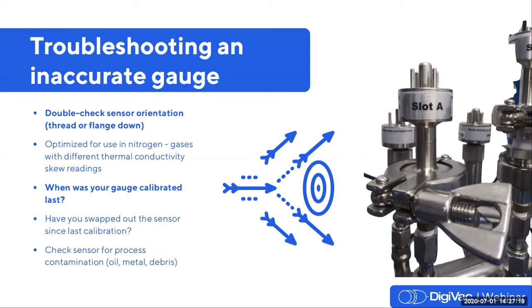If your gauge is still inaccurate, you can inspect the sensor for process contamination, such as oil, debris, or metal flakes. We use an otoscope in our facility to peek inside the sensor, which is a doctor's tool used for examining the ear, though other contamination can be seen with the naked eye or with the aid of just a lighted magnifying glass. If you find contamination inside, we recommend that you follow the cleaning instructions that will be outlined further on in this webinar. We will be putting on a full-length demonstration to follow in a future webinar, though we'll outline the 4 basic steps coming up.